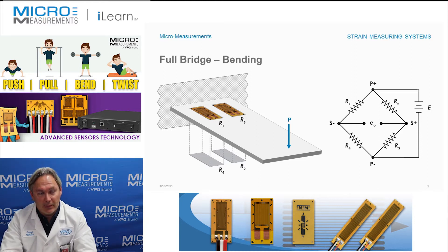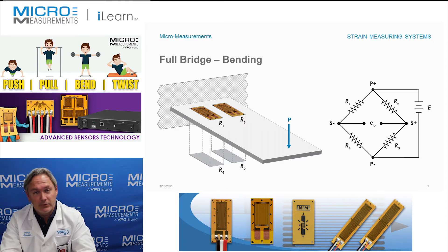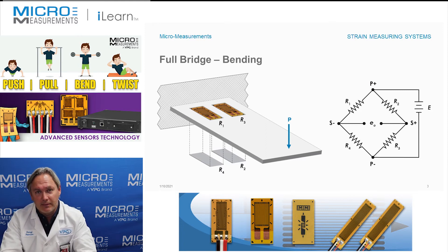When we apply load at the point given as P, these four strain gauges contribute effectively the same magnitude of signal. Let's assume we push hard enough to produce a thousand microstrain — we use a thousand because that's an easy number. So if R1 and R3 see a thousand microstrain of tension, R4 and R2 would see a thousand microstrain of compression.